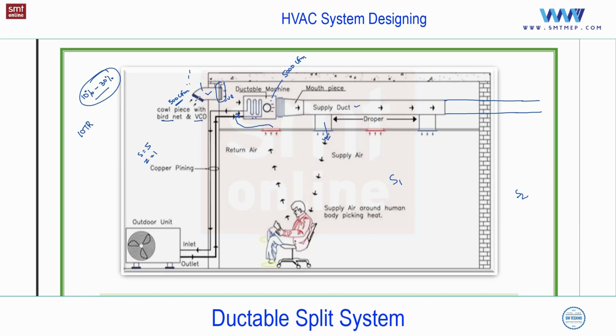So you see, I'm going to design this 500 CFM piece so that, say, supply of 5000, out of which 500 is fresh air. So return is going to be here. Suppose suction is 4500, 500 collected from here, again 5000. And the additional 500 that we are adding as fresh air, we need to exhaust.